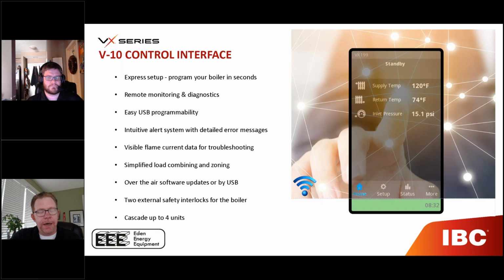What we like about that is you might buy a boiler this year, and then next year IBC might release a whole host of new features to those boilers. You aren't paying a penalty by being an early adopter. You can very easily update the software for that unit, which makes a really big difference. It also has 2 external safety interlocks for the boiler, and you can cascade up to 4 units on this V10 VX control.